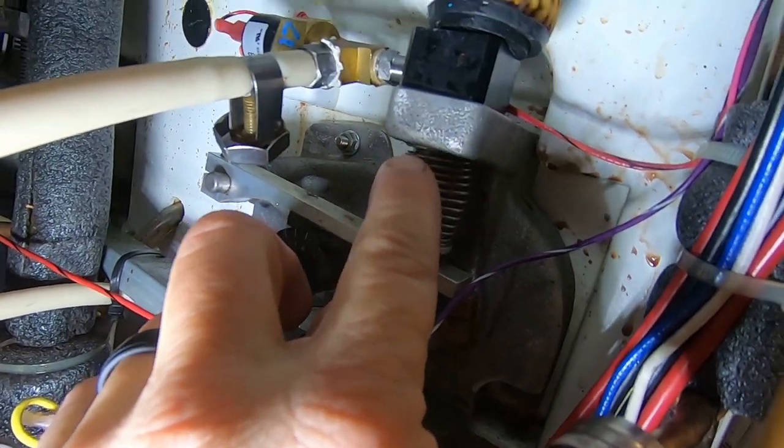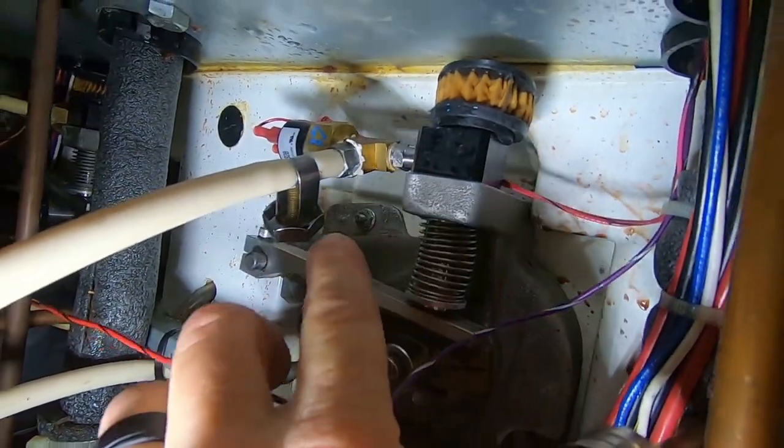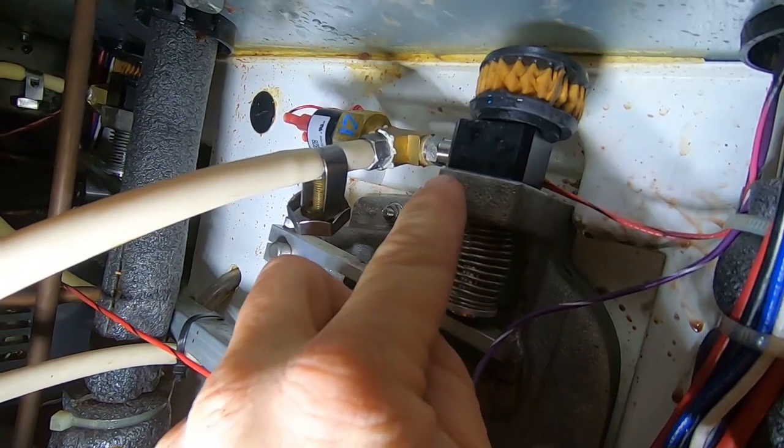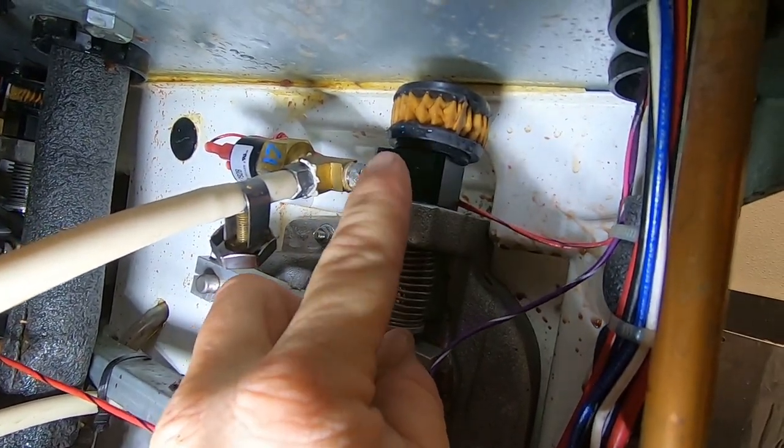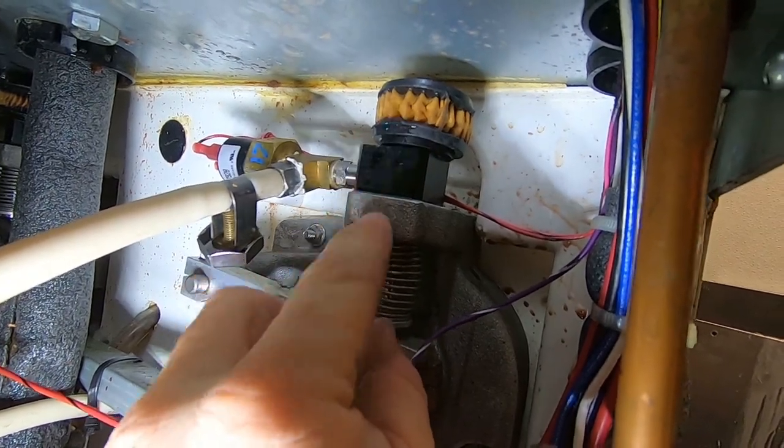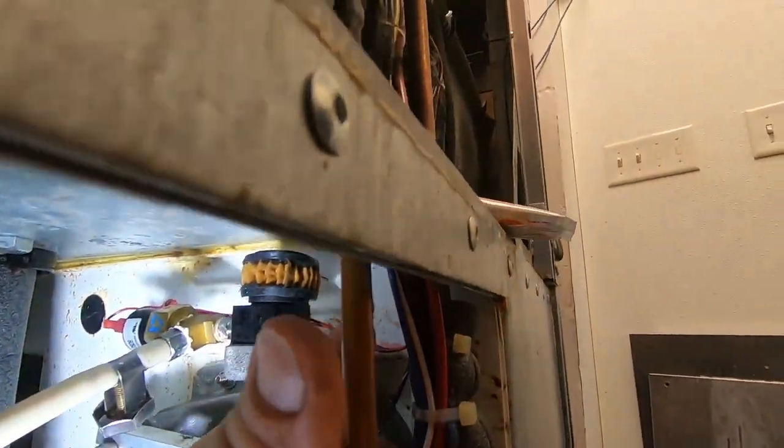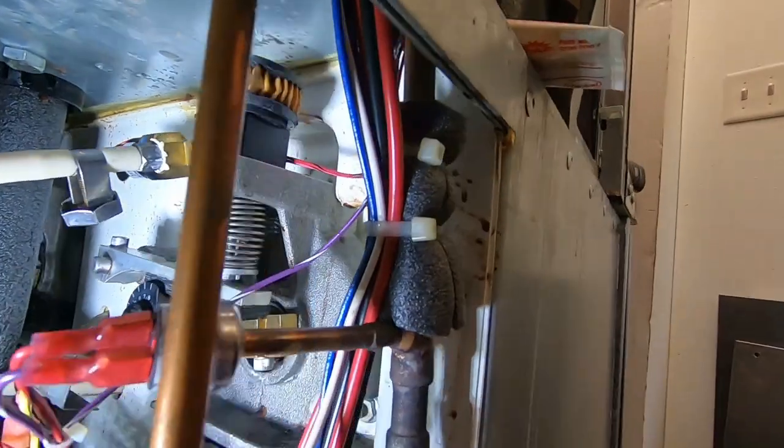This pump here has a tendency to be gummed up really bad. What happens is this stuff leaks, comes back in here. You got an air leak in here, it'll get back into the check valve which is that silver thing, the piston, all that gets gummed up full of crud, and then that's a bad day.